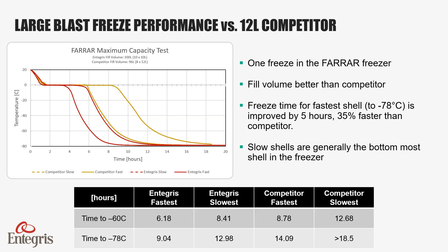So with a full freezer load, 35% faster only by changing the consumable type inside of that controlled rate chamber. And you'll see that the slowest freezing Entegris shell was actually still faster than the competitor's fastest solution. You'll also note that there is a lower variance from fastest to slowest in the Entegris shells than in the competitive product.